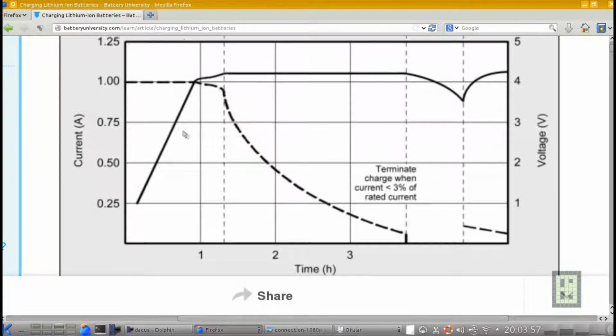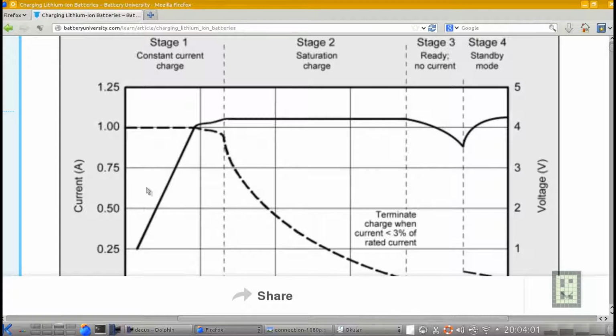It can vary. If you use a solar panel, the current will be limited by the amount of sun hitting the panel. So it can be 100%, say 30 or 40 amps, or it can be 10%, like maybe only 4 amps if there's a cloud for a few minutes. This is still constant current charging, because the battery voltage is increasing during charge, and the current level isn't what defines it. You'll still call it constant current even if it fluctuates with the amount of sunshine, and the battery life won't be affected by that.